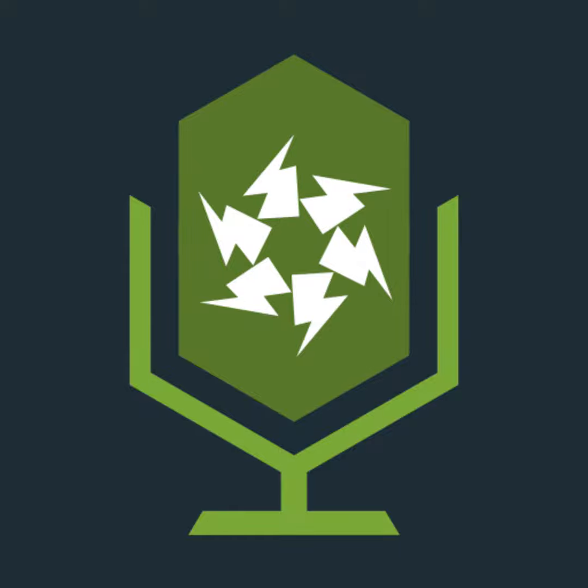For the IT system, overcurrent devices, when used as devices for fault protection in the event of a second fault. Let's remind ourselves about the IT system. The IT system is a specialised earthing system where we establish a high impedance between the earth and the supply live conductors, so if there is an earth fault current flowing, so there is an earth fault condition, that high impedance results in a very, very low current, a current value that will not cause harm.